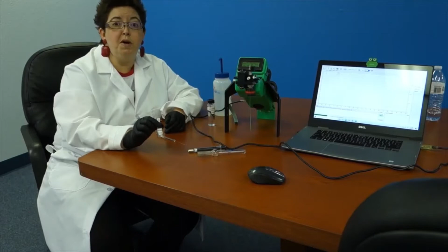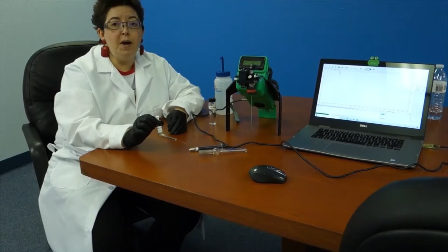Okay. The purpose of this is to run known samples of concentrations of your analyte. Okay. Here today we're using MTBE and BTEX. Okay. So you want to run known concentrations, and we're going to use those known concentrations to build a calibration file. Okay. Here at Defiant, we prefer to use a minimum of 5 points for our calibrations. We strongly recommend that you use a minimum of 3 calibration points for a linear fit or 4 for a quadratic fit. Okay? If you don't know what I'm talking about, just bear with us. We're going to cover that in detail.